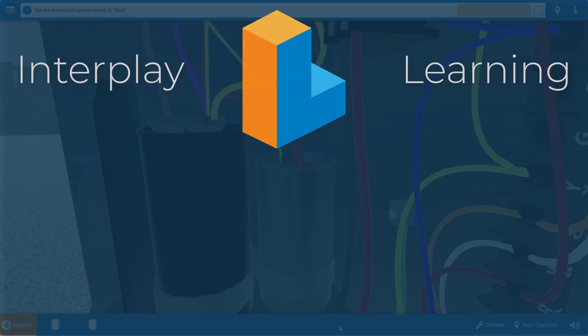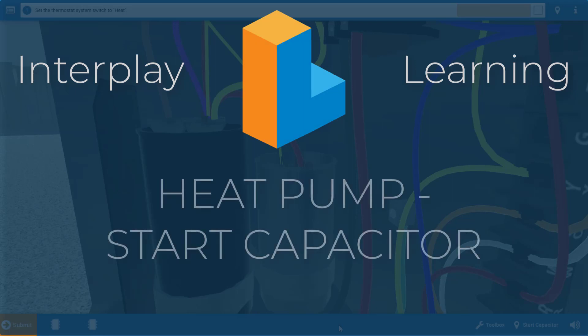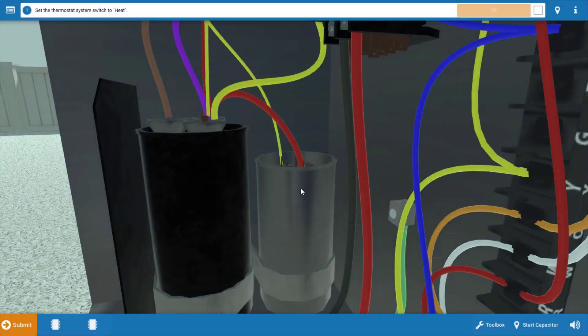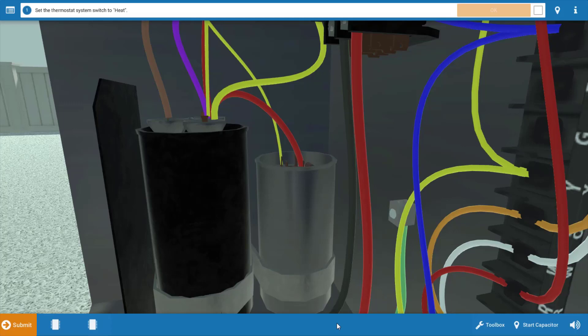Hi, my name is Tim, and in this video, I'm going to guide you through the proper procedure for diagnosing a faulty start capacitor on the heat pump simulator. Now, this is the start capacitor right here, and it's in series to the start winding of the compressor and provides starting assistance for the compressor.